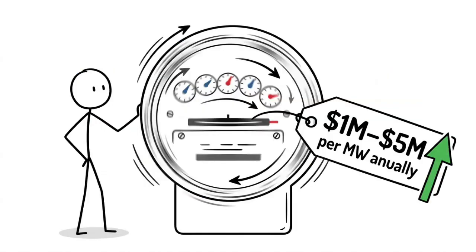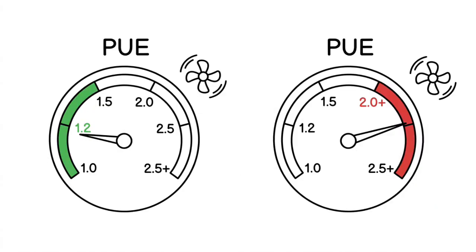Once it's running, the cost structure shifts to something more predictable, but still brutal. Electricity is the largest recurring expense, running $1 to $5 million per megawatt annually, depending on region and efficiency. Operators live and die by a metric called power usage effectiveness, where a well-run facility hits close to 1.2, and an inefficient one can run above 2.0, meaning it burns nearly twice as much power on cooling and overhead as it delivers to actual computing.